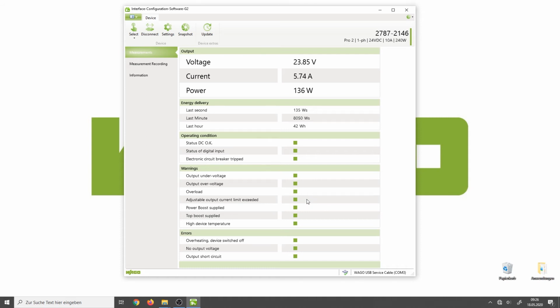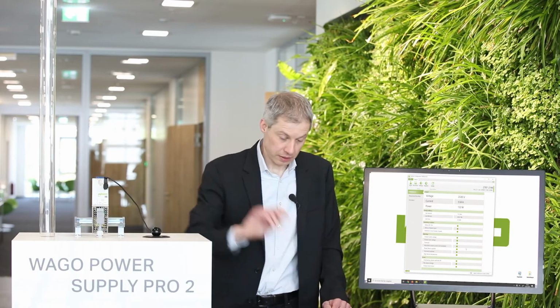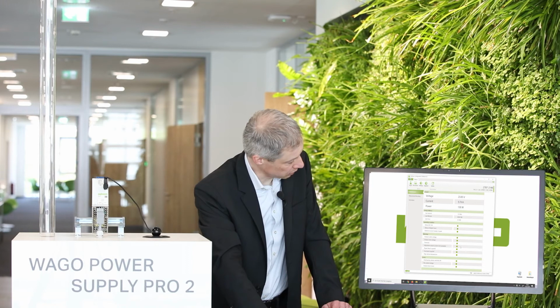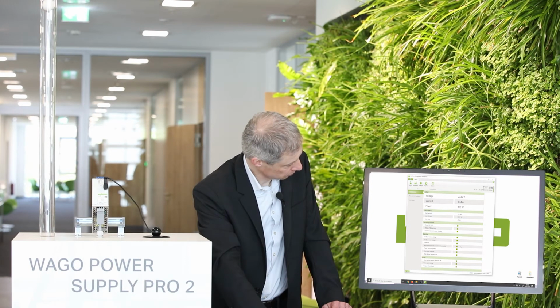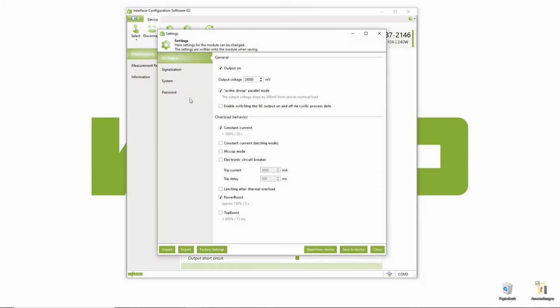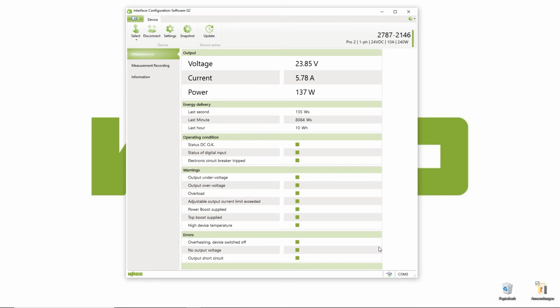And now it is green, that means everything is fine, but as soon as we have a higher output current, the light will turn to red, and it says that the limit of the output current has been exceeded. If we want a certain overload behavior, we can do that also in the settings menu. And here under the DC output menu, we see different overload behaviors. If we set it to electronic circuit breaker, we can choose here, for instance, 8 amp and 5 seconds. And we say save to device. And now the output is configured as a single channel electronic circuit breaker.